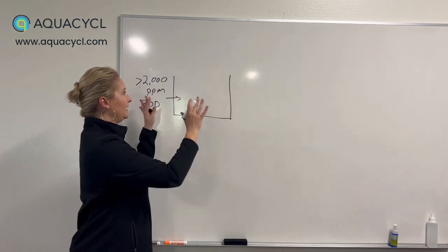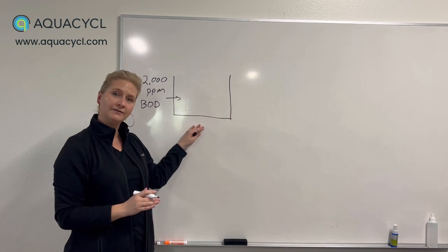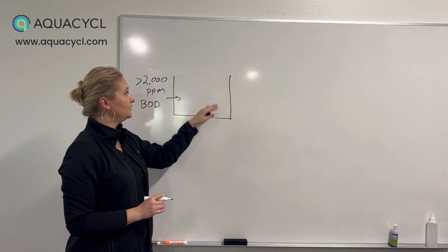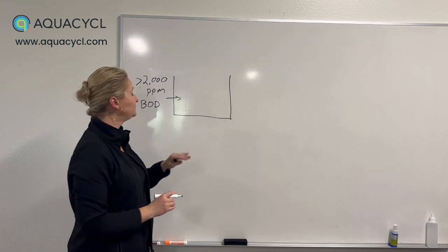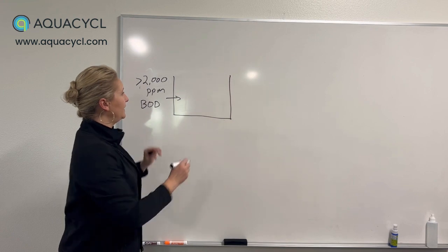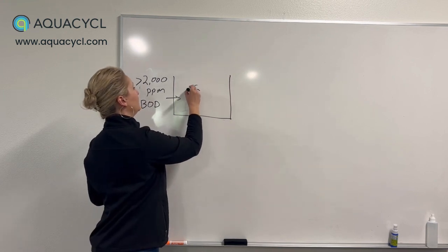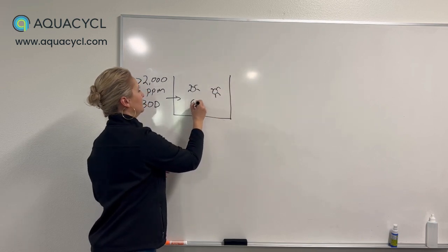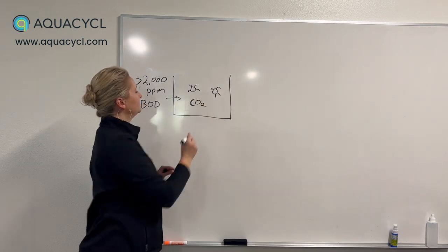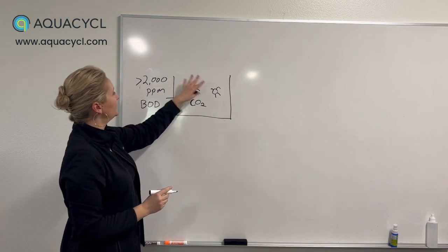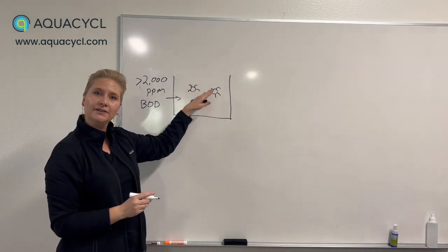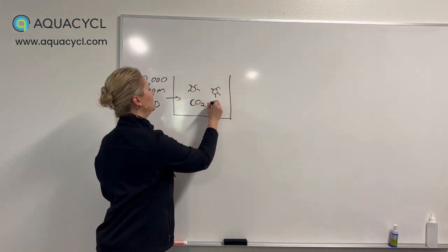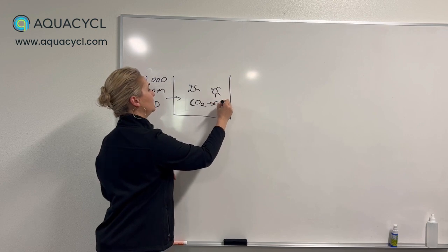And so what's happening here is you're not forcing oxygen anymore. There's no oxygen going to be present in this tank, but you do want to have a source of CO2. And what is going to happen in this tank is your bacteria, different types of bacteria now than were in our aerobic tank, right? They're going to take that carbon dioxide and they're going to consume the organics coming in, so that's their food source. But now their respiration source is actually fixing CO2 into methane, CH4.